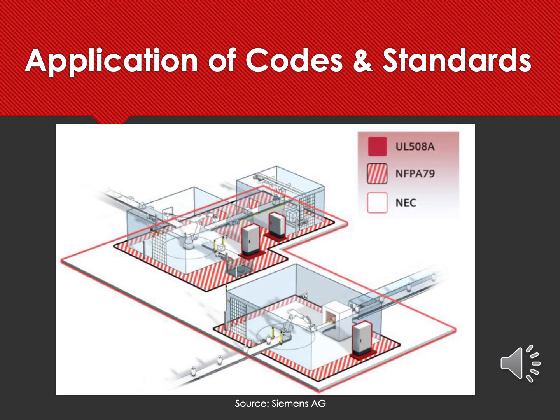This slide shows a quick graphical representation of the application of these three codes and standards we discussed. First, all the equipment, machinery, panels, and connections to this equipment in the solid white area have to adhere to the NEC installation code requirements, or NFPA 70. The shaded red area shows the industrial machinery space, which has to follow the NFPA 79 machinery standard. And the solid red area shows the industrial control panels within the machinery area, which have to comply with the UL 508A standard. Let's go to the next slide.